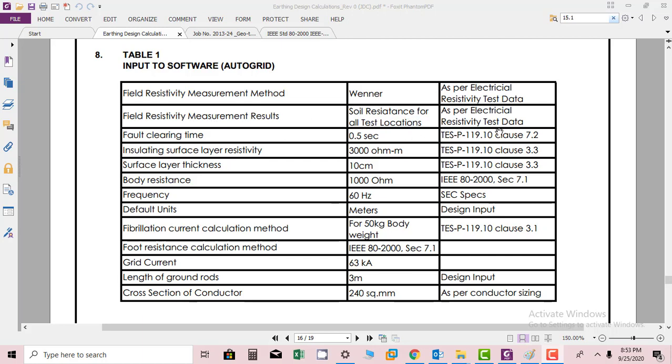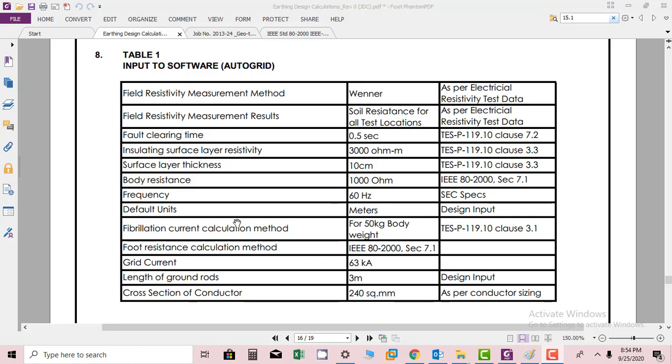Fault clearing time we are using in the software is 0.5 seconds. Insulating surface layer resistivity we are using is 3,000 ohm-meters. Surface layer thickness is 10 centimeters, body resistance is 1000 ohms, frequency 60 Hertz which is depending upon the system. Default units is meter. Fibrillation current calculation method is 50 kg of the body.